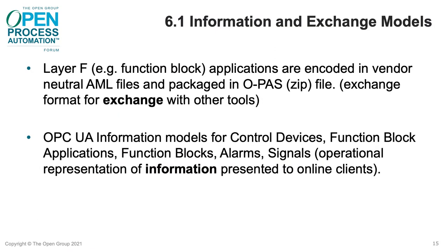Part 6 is about information and exchange models. An exchange model represents design information that can be shared with other engineering tools. An information model defines how operational data is organized and communicated to online participants over the OCF. Layer F function block applications are encoded in vendor-neutral AML files and packaged in Open Packaging Convention OPAS zip files. OPC UA information models are defined for control devices, function block applications, function blocks, alarms, signals, and other things.